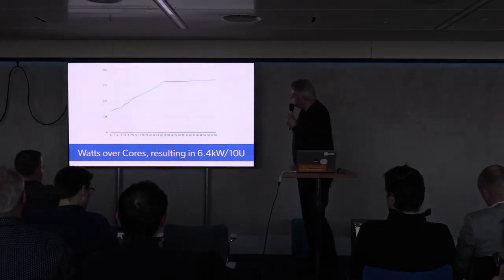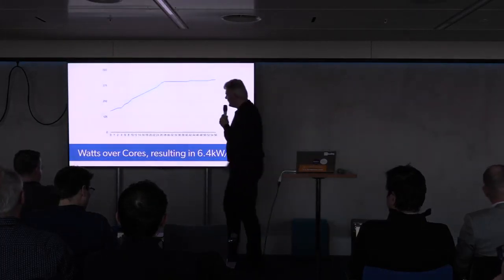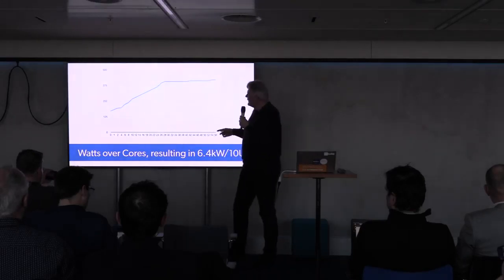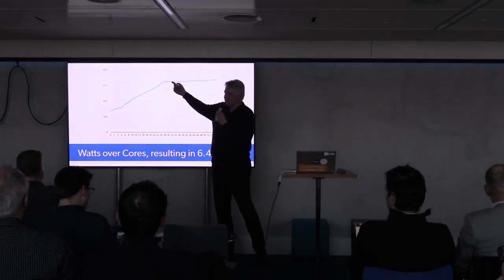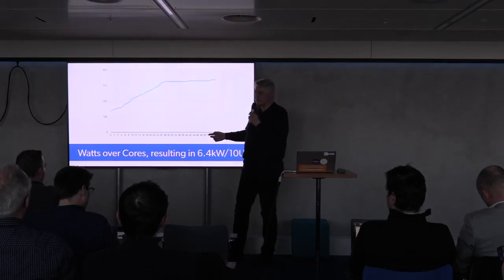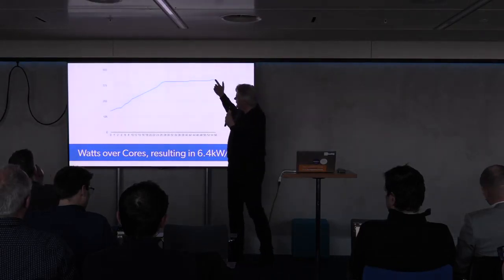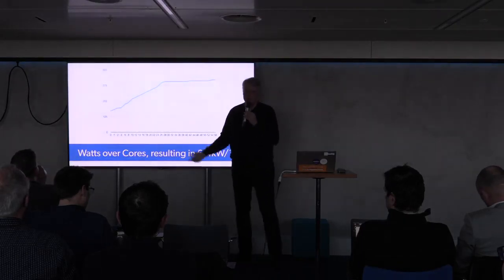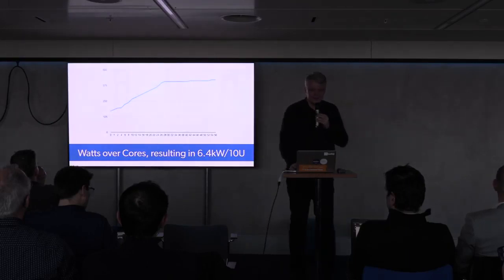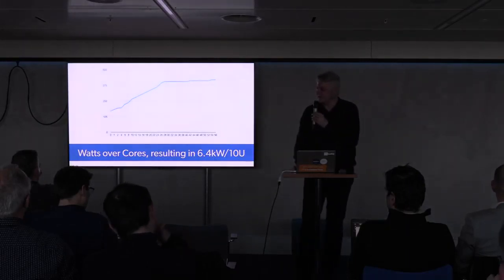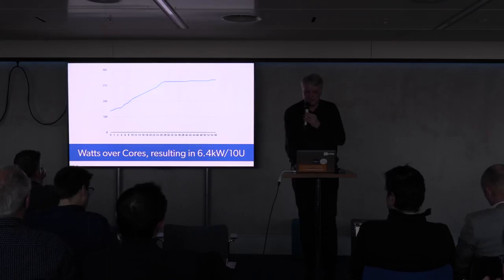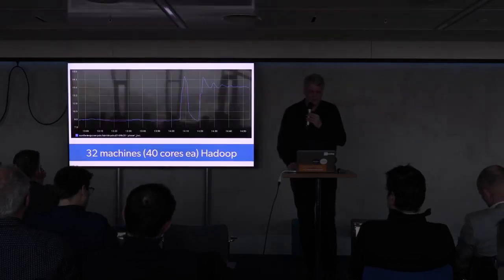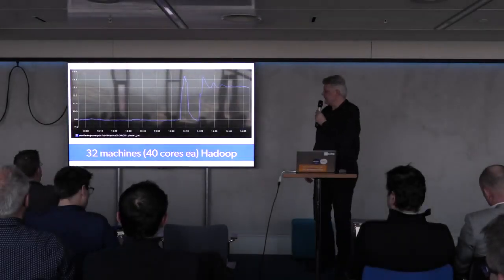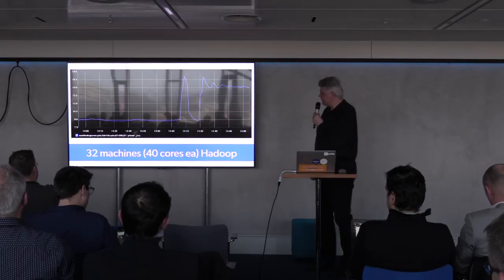That's a load test for such a 2690 in this case. I've been measuring the power consumption over the number of cores kept busy. If you look at the total power draw here and multiply that by 16, you end up with a 6.4 kilowatt chassis and a 7 kilowatt rack, and then it's game over. That is a rack of 40 machines.